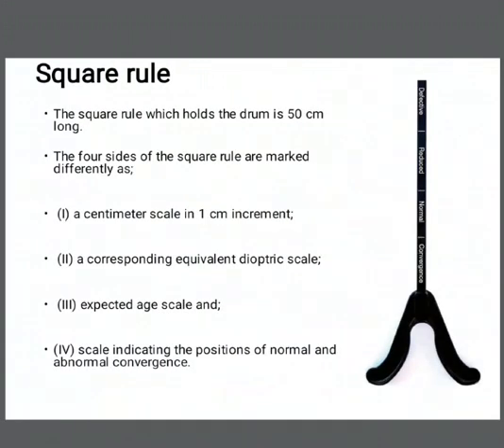The square rule is 50 centimeters long and holds the drum. The four sides of the square rule are marked differently: a centimeter scale in one centimeter increments on the first side, a corresponding equivalent dioptric scale on the second side, an expected accommodation scale on the third side, and a scale indicating the position of normal and abnormal convergence on the fourth side, as seen in this figure.